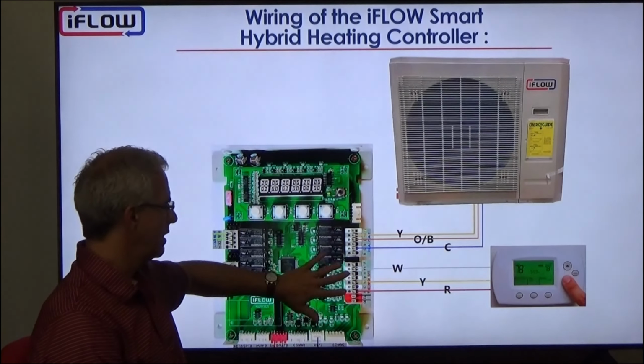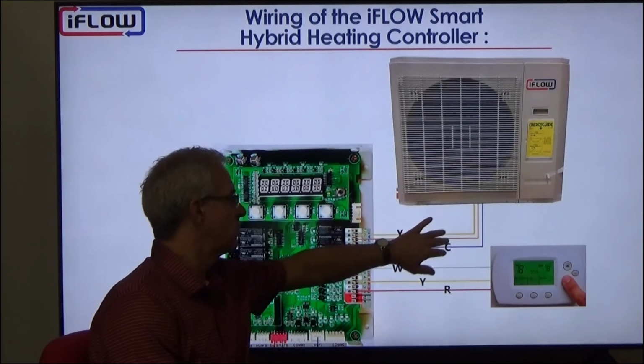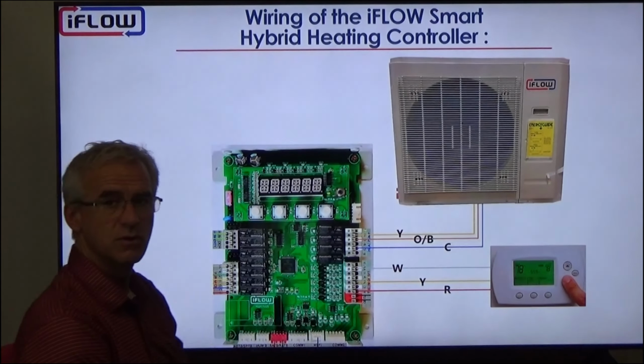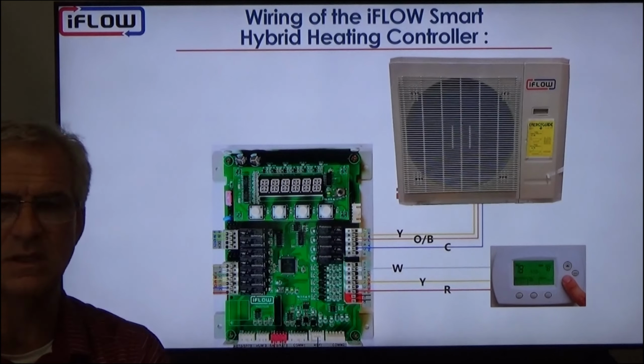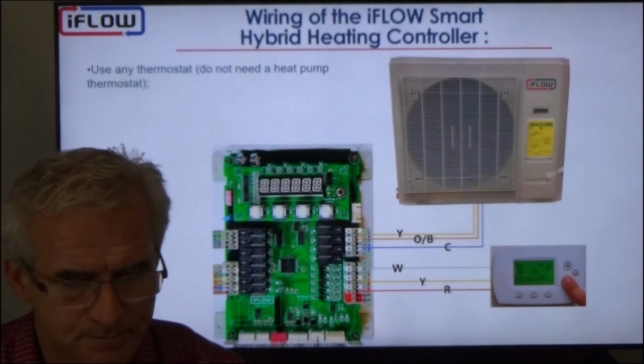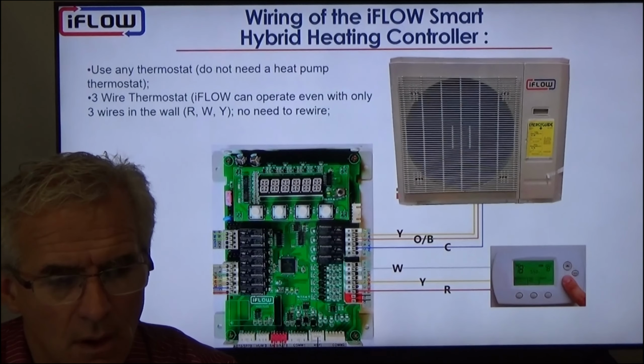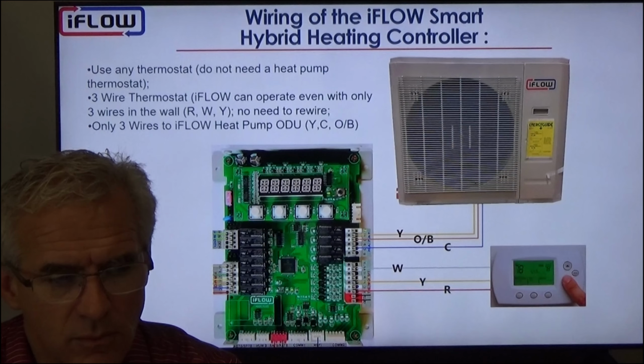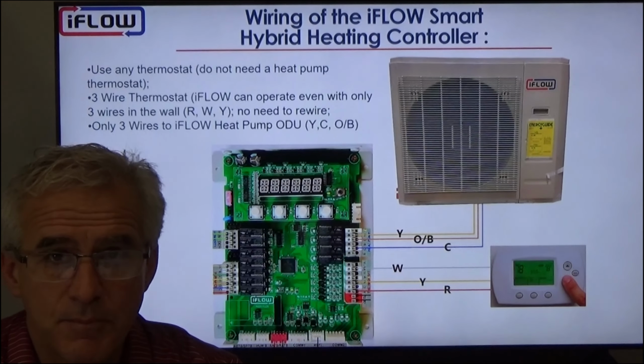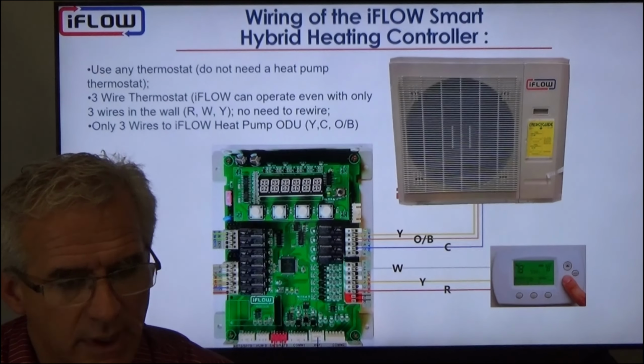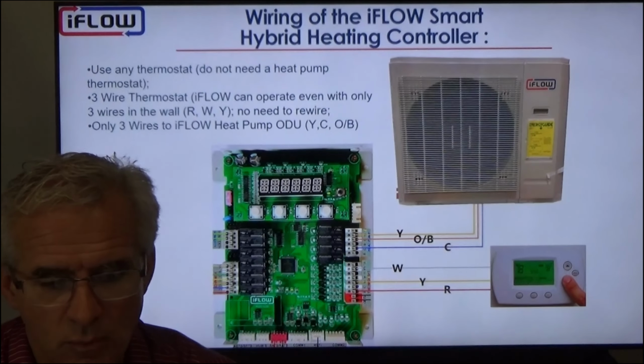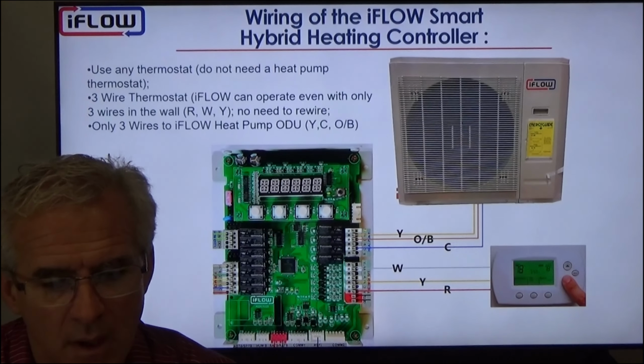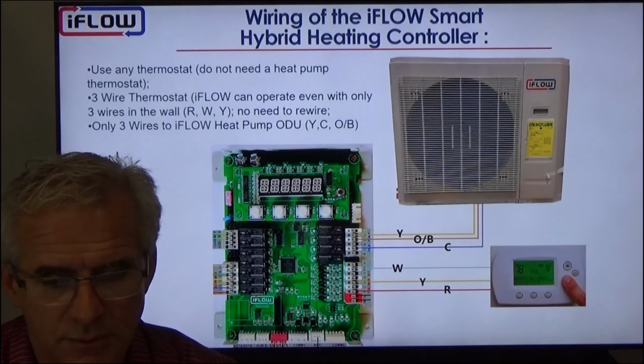We bring the 3-wire into our controller, and again we send the 3-wire out to our condenser unit. So again, the wiring is very simple, very easy with the iFLOW system. We don't require any heat pump thermostat. Only a 3-wire thermostat will work fine with our system, and then 3 wires out to the outdoor unit.